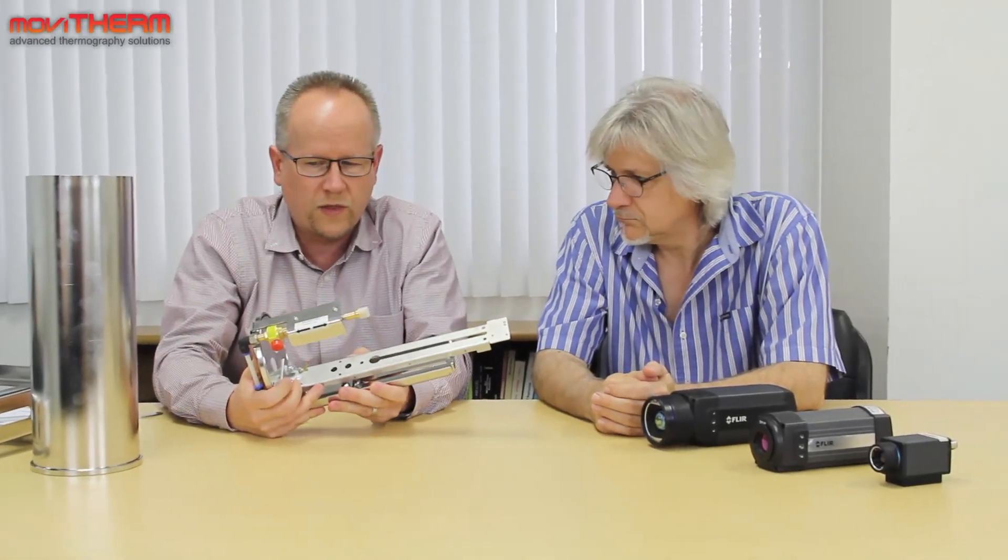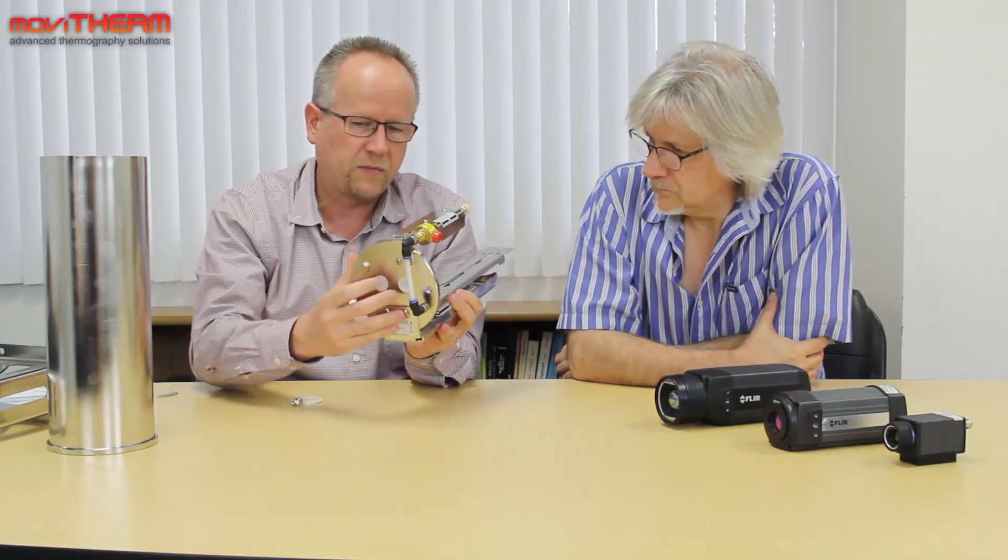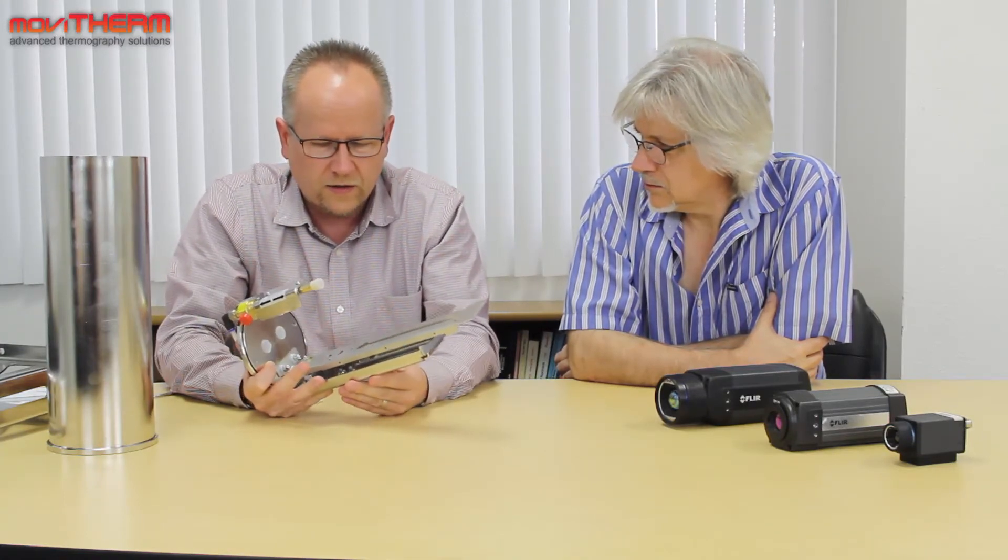On the bottom side is really the mounting surface on the outside of the enclosure and it's also coupled with a mounting bracket that slides on the inside of the enclosure all in one piece which is kind of comfortable and advantageous when you want to mount the camera or service the camera. You can just pull everything out in one shot. We have this mounting bracket that holds the vortex tube, mounted all in one piece, so everything comes out and slides out in one piece. There's a couple of plastic plugs in here where the cable glands are going to be. Then the mounting bracket with a little lug to connect the earth ground to it and a long slot here to adjust the camera position because some cameras are longer than others.